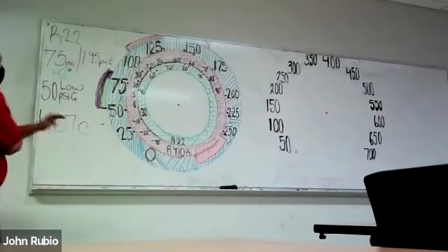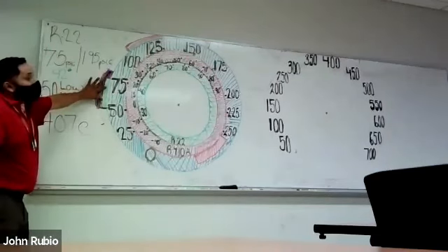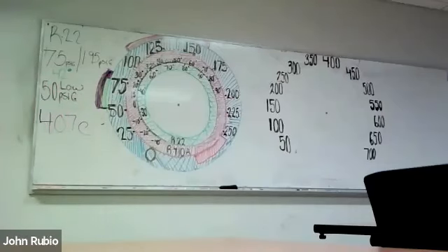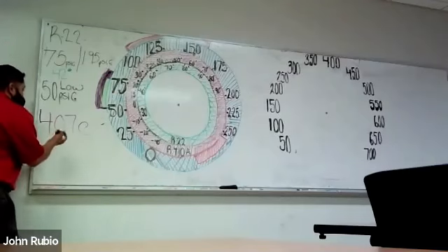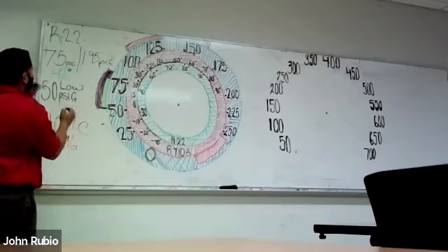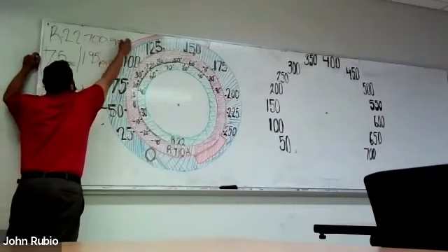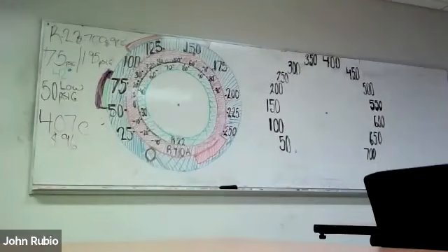I was told that in the beginning, when you wanted to switch to 407C, you would have to take all of your R22 out. You had to replace a metering device. It wasn't just plug and play. There was a lot of work to use 407C instead. The trade-off is 407C. I think I just bought a jug of it and it costs $96. And it works for R22. Real R22, 700 to 900 per jug, 25 pounds. It's quite the price difference. That's why we developed the 407C.